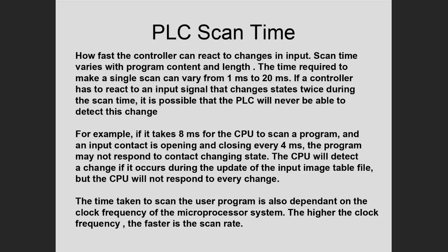I talked about the fact that for all this stuff to happen, the switch has to open or close. The processor has to read the status of that switch, whether it's open or closed, and then it has to store that binary information. The status of the switch is a 1 or a 0. It has to store that in the data table, and then it has to go and look at your program. All of that takes time. So the idea of program scan time is really, really important.